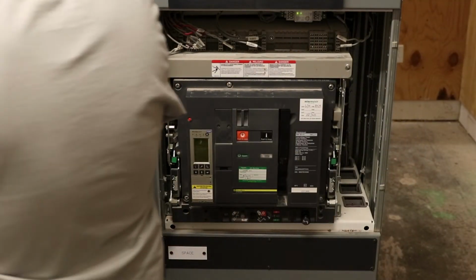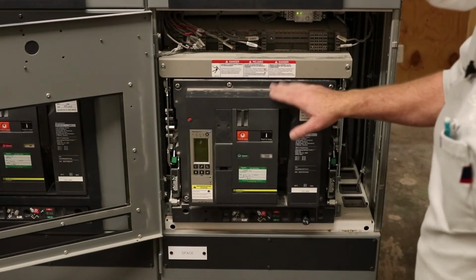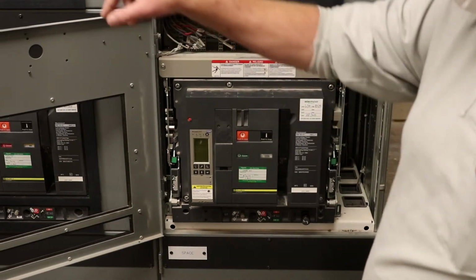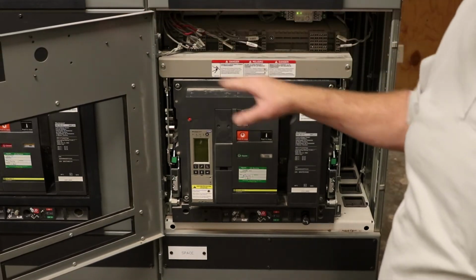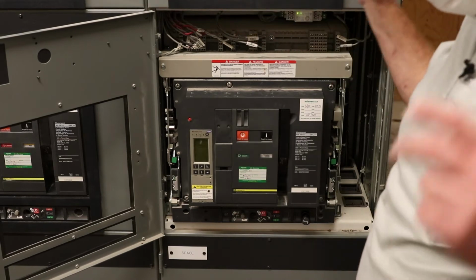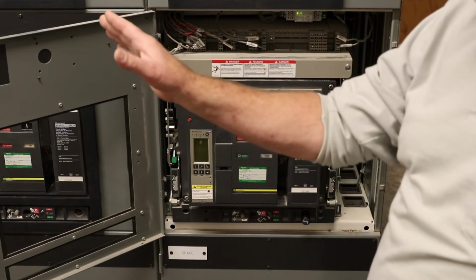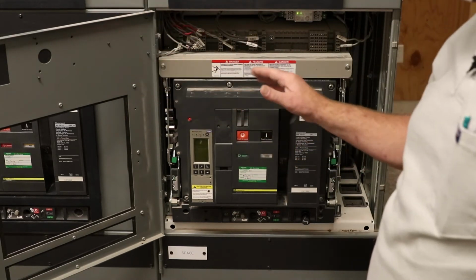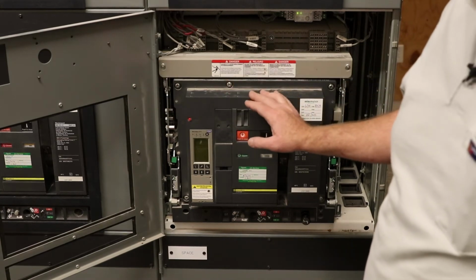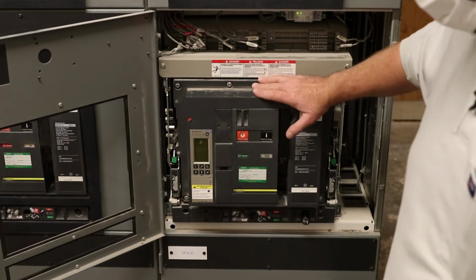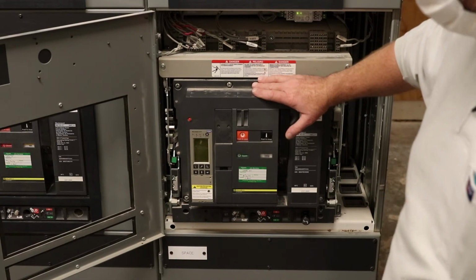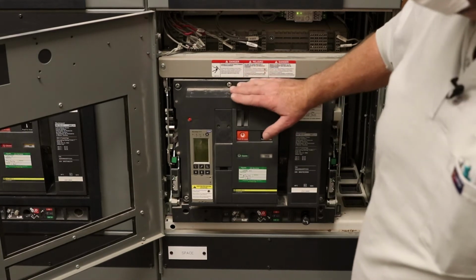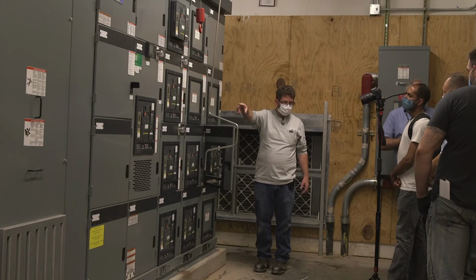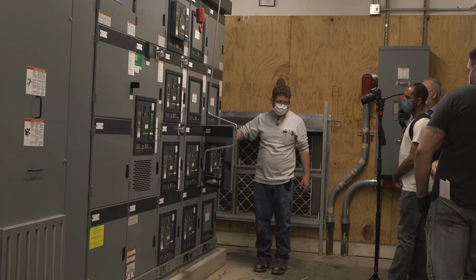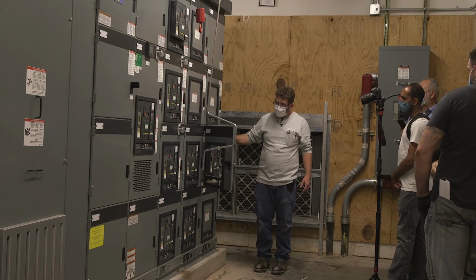This is a 1600 amp breaker. You couldn't put a 1600 amp breaker in here. You may or may not be able to put the 800 amp breaker in there because it's not a code violation to put an underrated breaker in a cell. It is a code violation to put an overrated breaker in the cell because the bus supporting this breaker is not built to withstand or to hold up to 1600 amps. So you couldn't put a 1600 amp breaker in there.